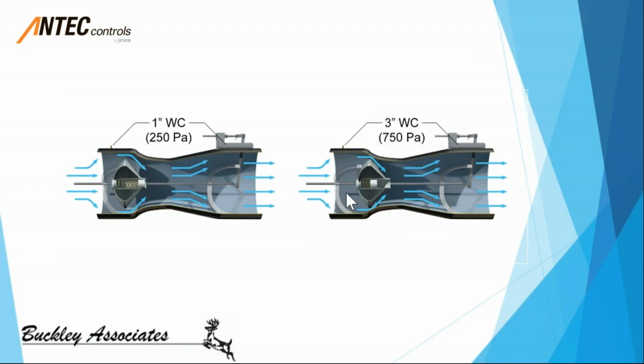Okay, on the right side here, we see the same valve in a higher 3-inch static condition. This is where the spring is now compressed due to more pressure at the inlet of this valve. The orifice size here is reduced. However, due to the increased pressure, we're still allowing a constant flow through this valve. So even though I don't have a specific CFM, let's say we're allowing 500 CFM through this device on the left side. This is the exact same. So we're looking at 500 CFM coming out on the right side as well, even though we had a pressure change.